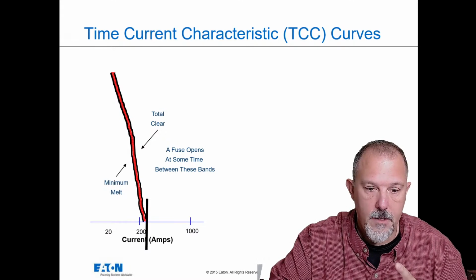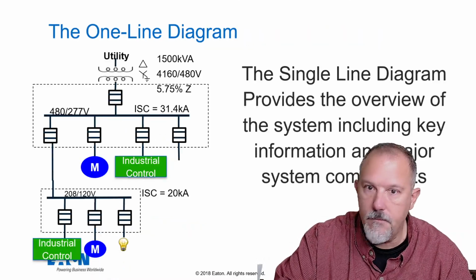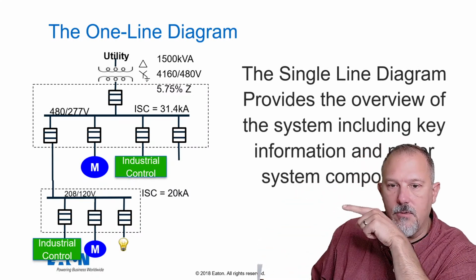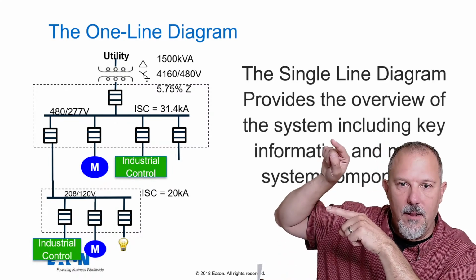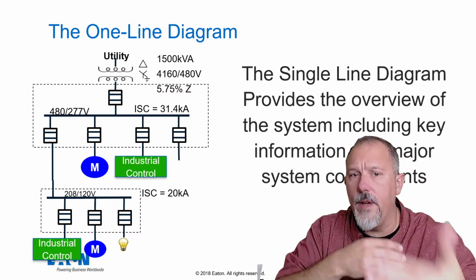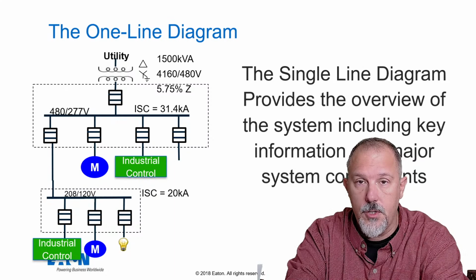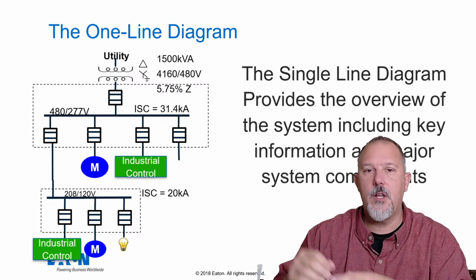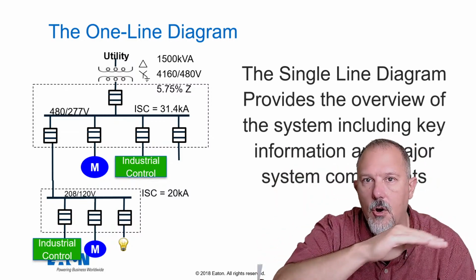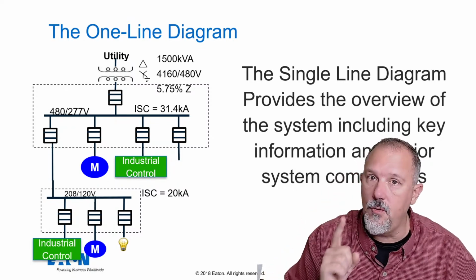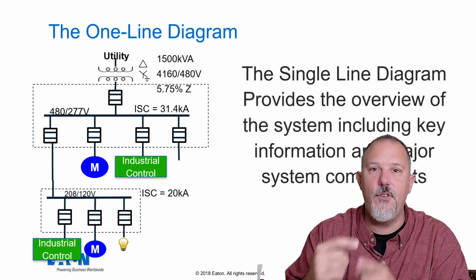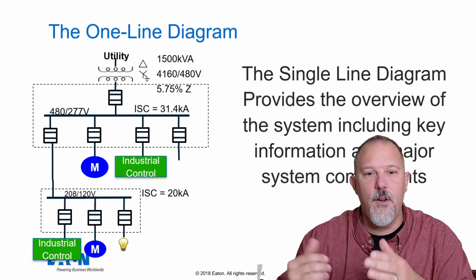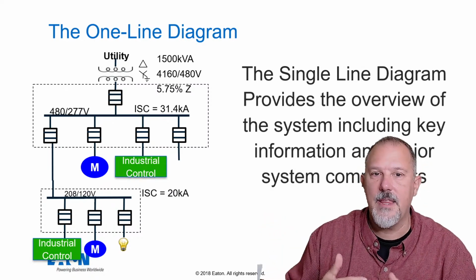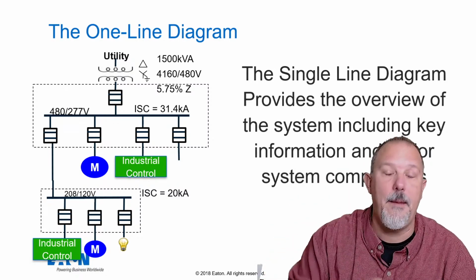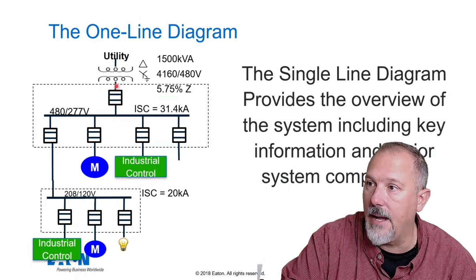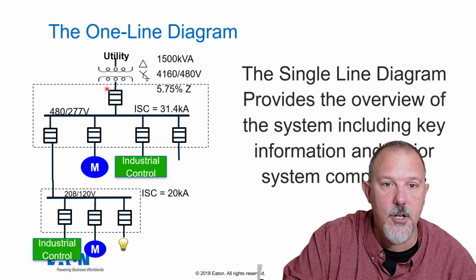Now, understand please that when you're dealing with a one-line diagram, the fault current at this panel down here is less than the fault current in that panel up there. The further you move away from the utility, we add conductors, we add transformers. You can't assume that because I have a fuse on the main, it reduces the RMS current throughout my entire power distribution system, because depending upon where the fault is in the system, that fuse is not going to respond to the same current. For a fault at this panel down here at the bottom, I'm going to have 20,000 amps, which may or may not be in the current limiting region of that main fuse upstream, this guy right here.